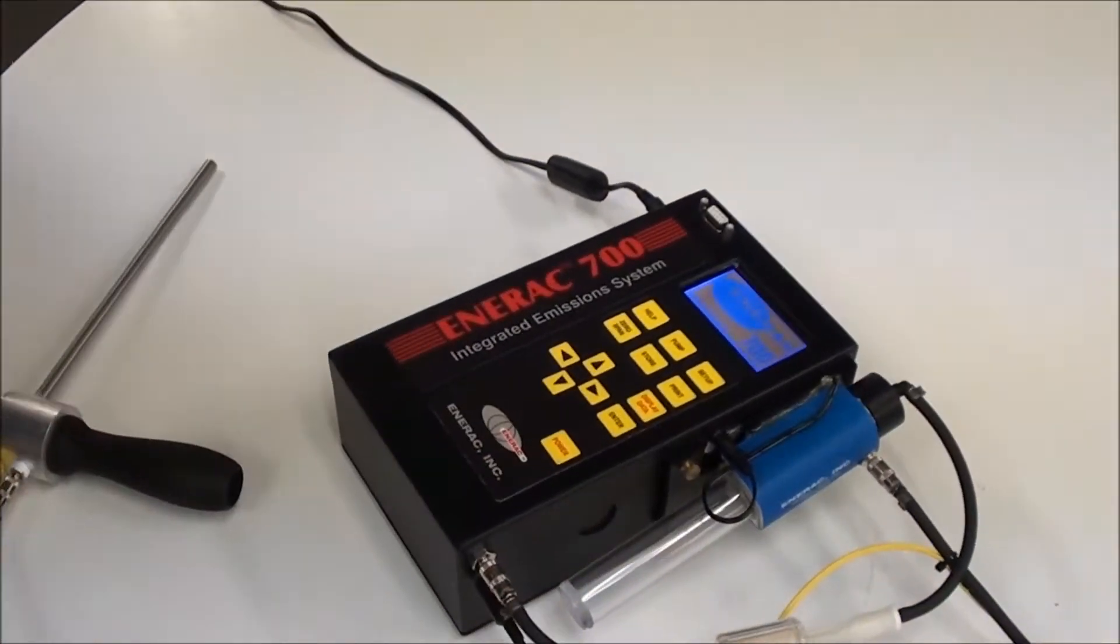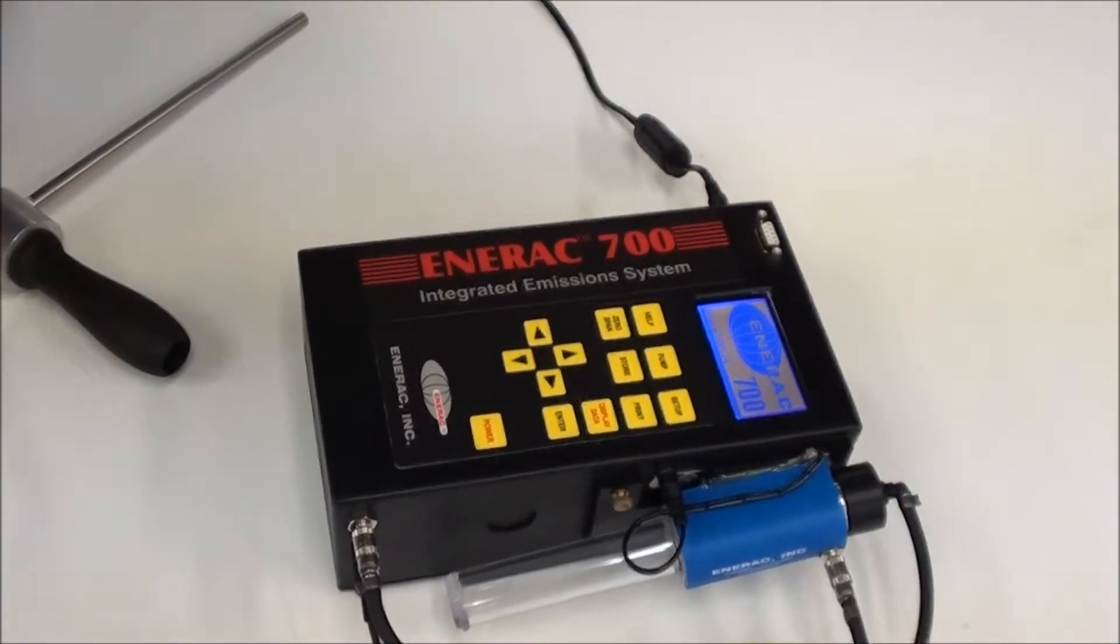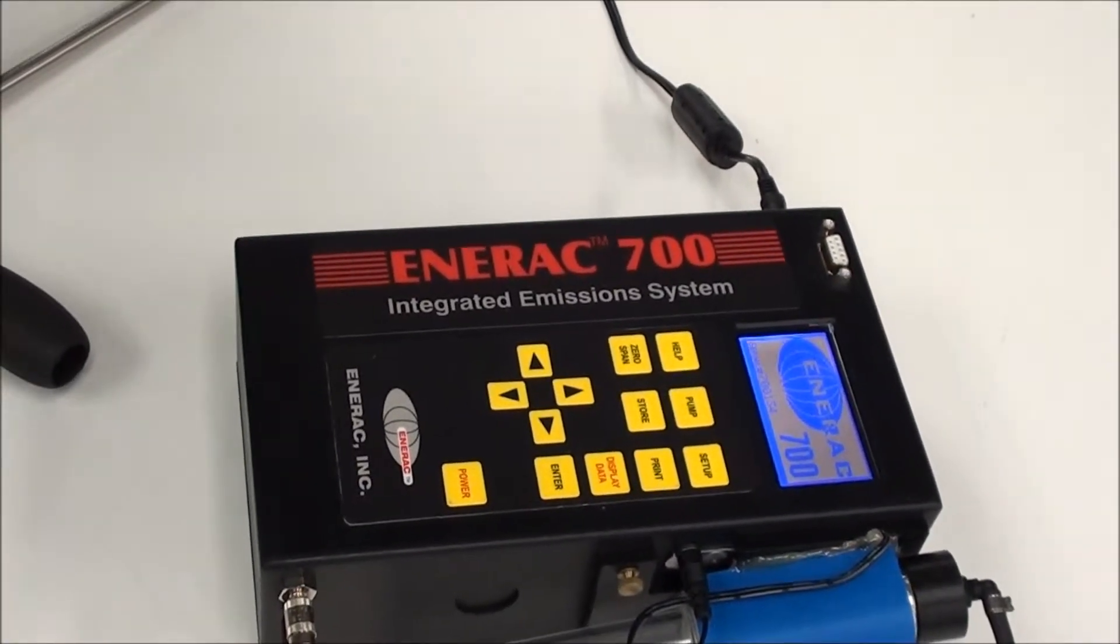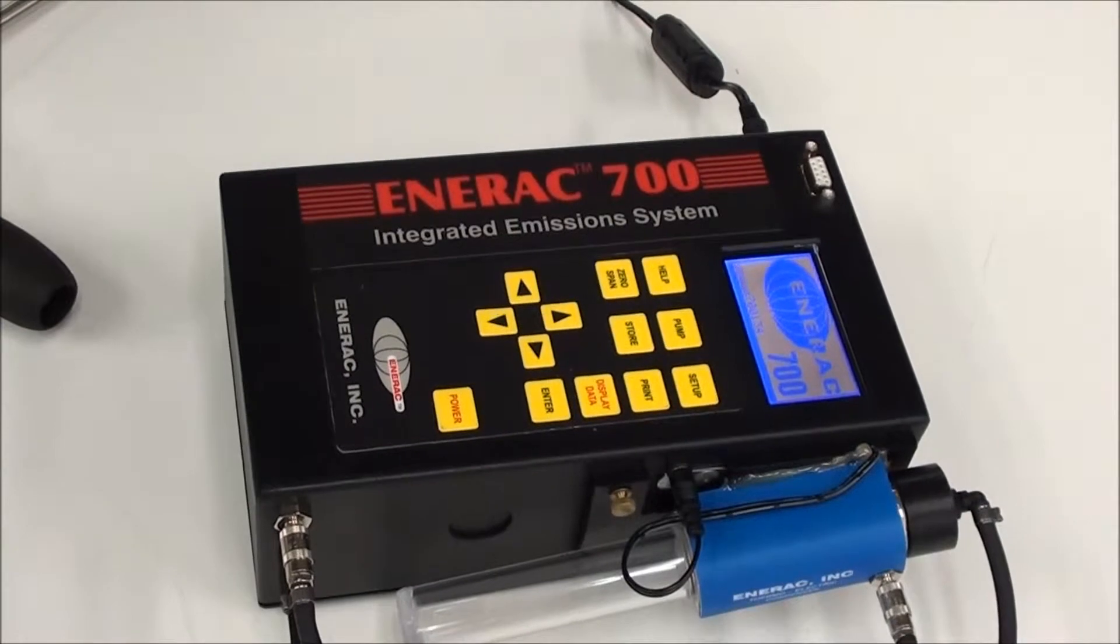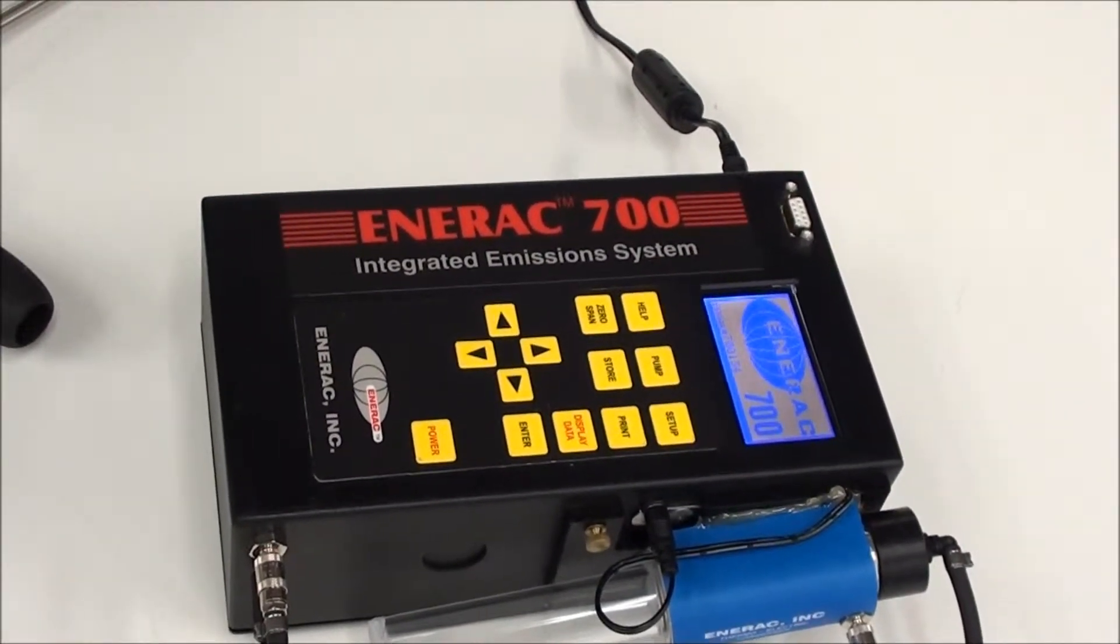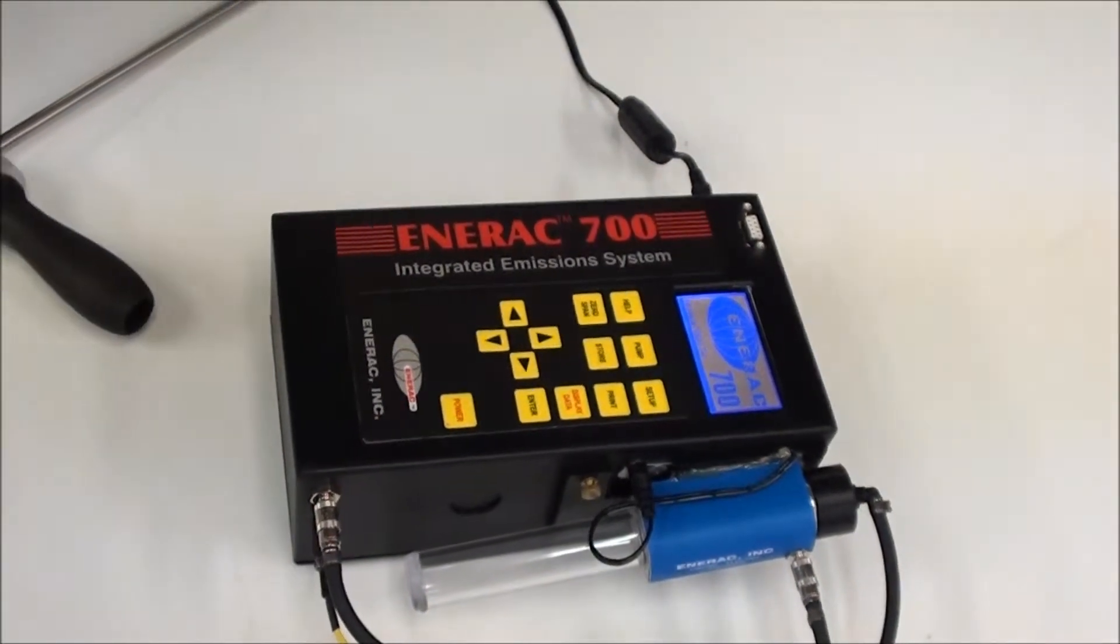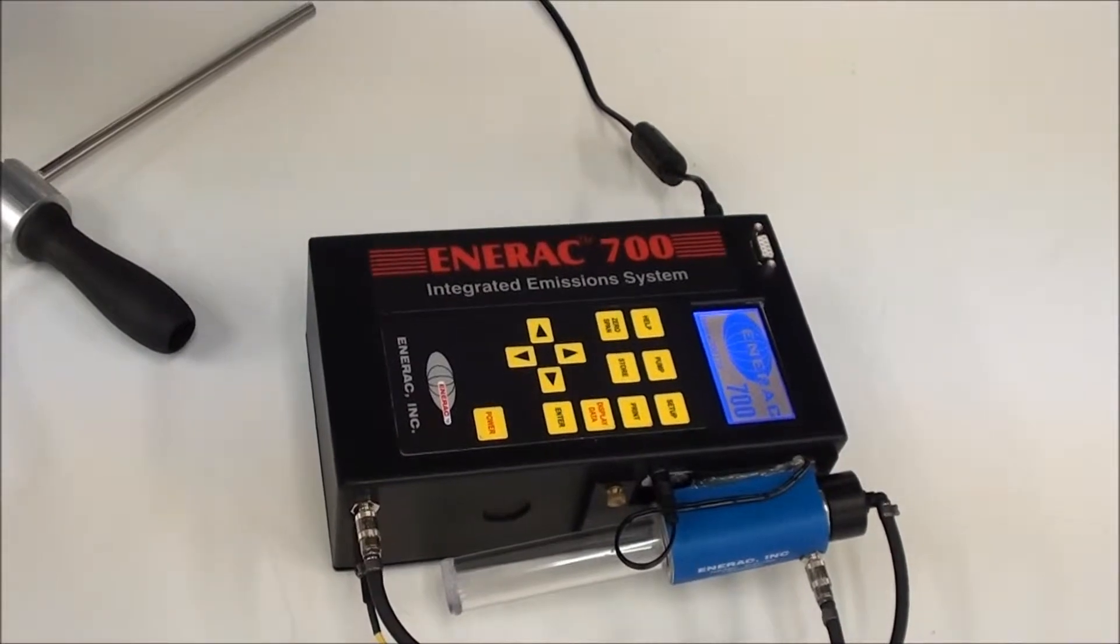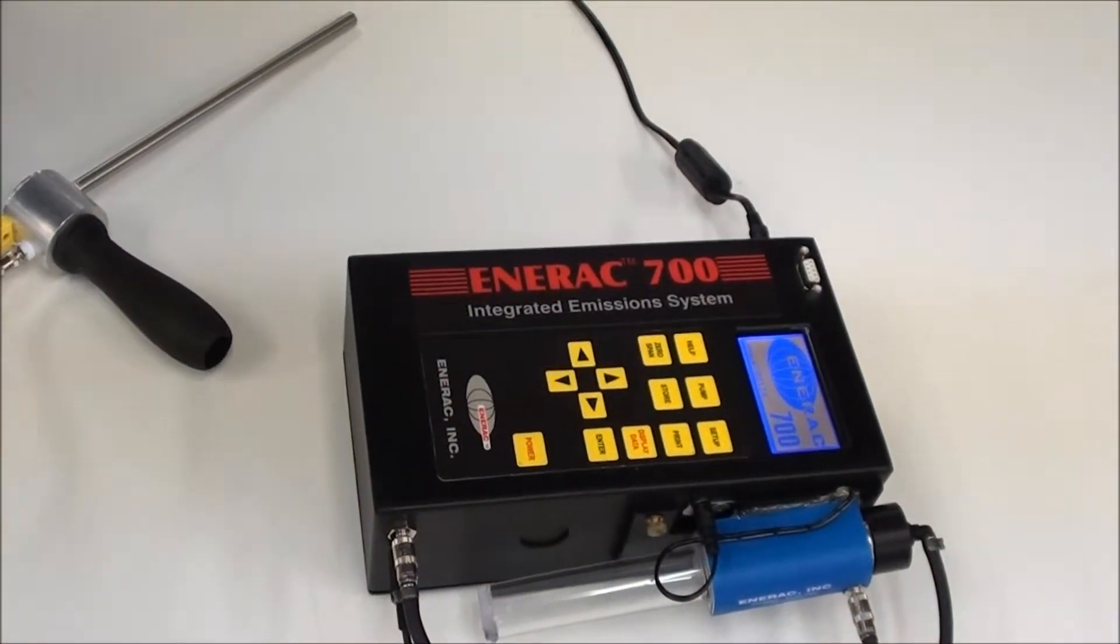So we power up the instrument. We just press the power button and what's recommended is to let it run for about five to ten minutes before we do an auto zero on the instrument. Auto zeroing will take a reading of all ambient levels of gases and temperature and so forth and set that as zero point. You want to make sure you're in a clean environment when you do the auto zero.